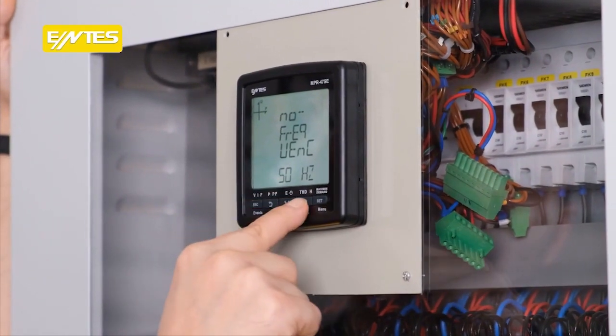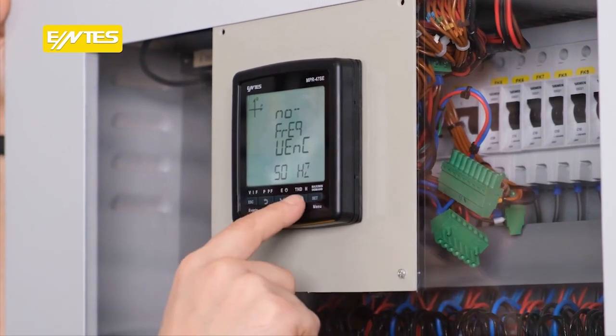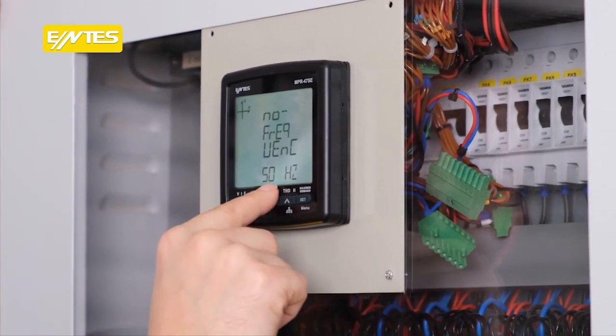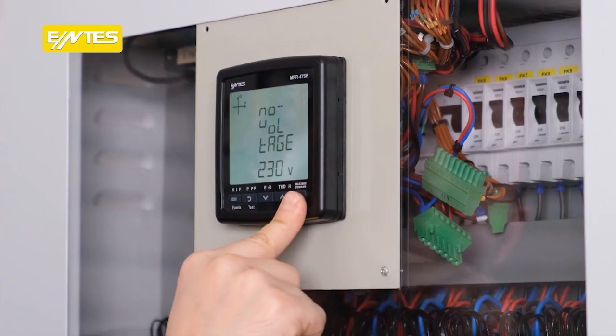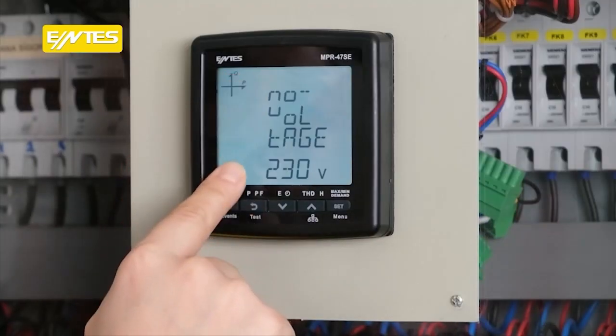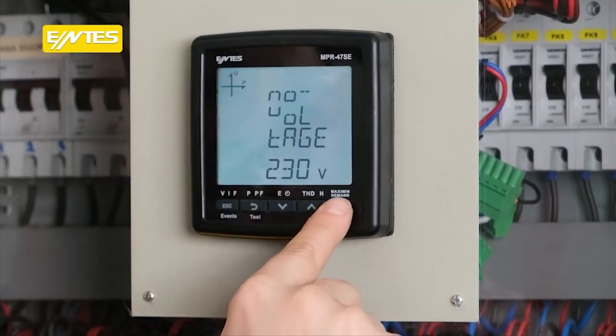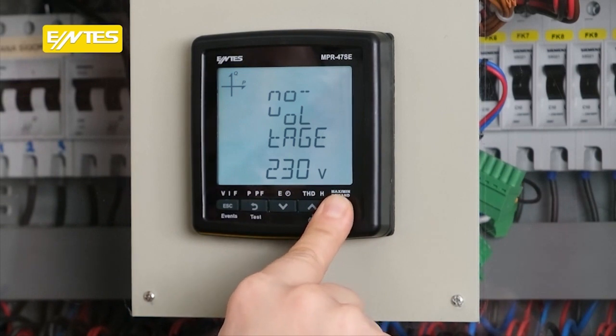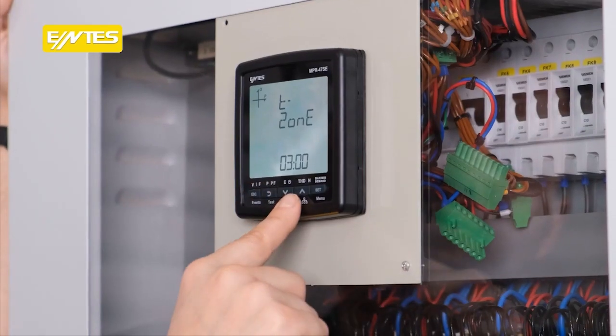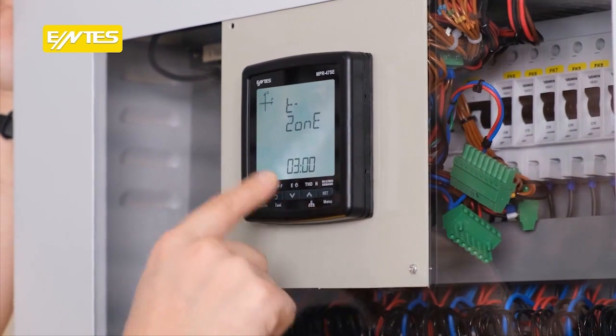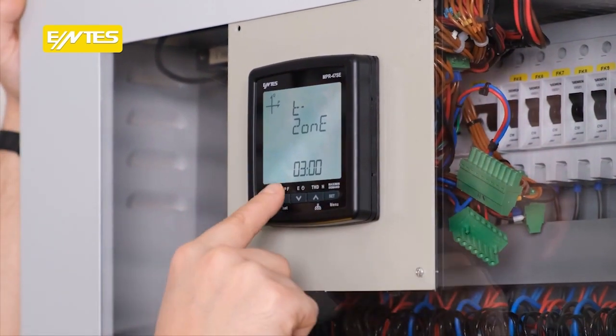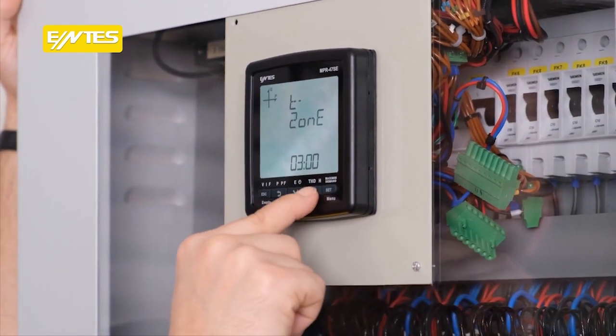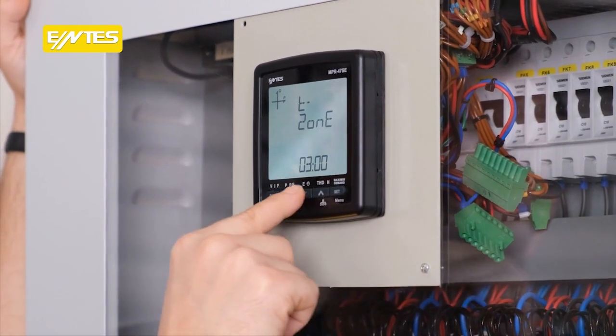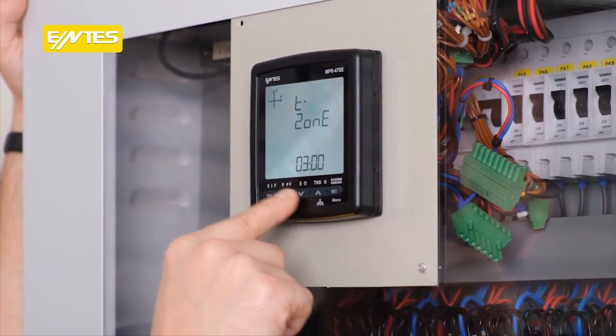The frequency setting is requested. Our device supports 50 Hz and 60 Hz. Because we use 50 Hz, it flickered at 50 Hz. We started. There is a voltage here. This voltage is constant, 230 volts. We are moving forward. Look at the time zone in the province and region where we are. If we are in the country, we need to enter the GMT time zone that we are in here. We can set it from here.